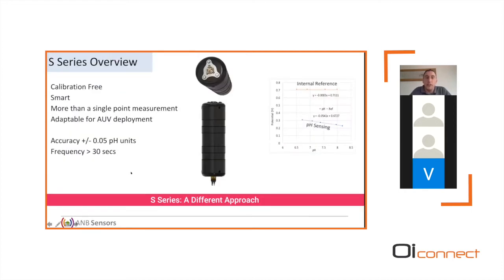So an S-series sensor is calibration free, it's smart, and I'll tell you why it's smart in the next slide. Rather than a single point measurement, it will give you a whole range of points, so it can tell us in situ what's happening with the sensor. We've made it adaptable for underwater vehicle deployment. Initially, we're looking for an accuracy of about 0.05 pH units. This is very much something that we're looking at developing as we're going through a transition into commercialization, and measurement frequencies of 30 seconds. But that's again something that we're looking to optimize over the next 6 months or so.